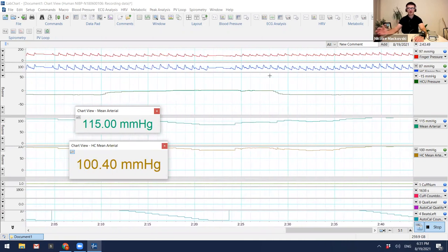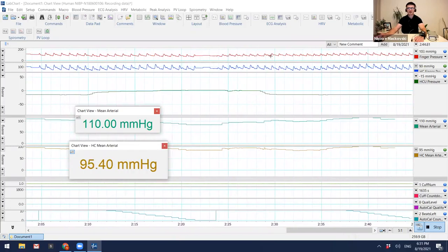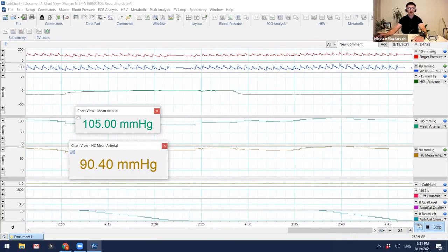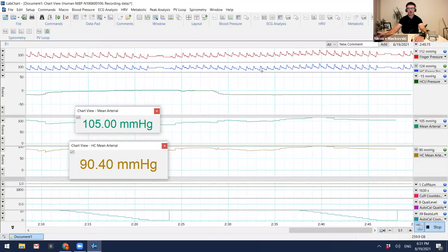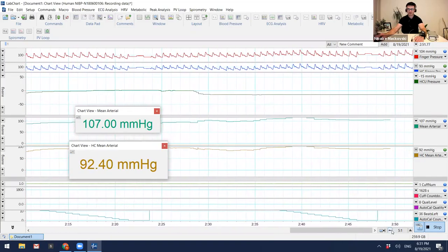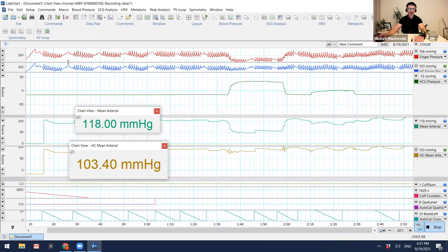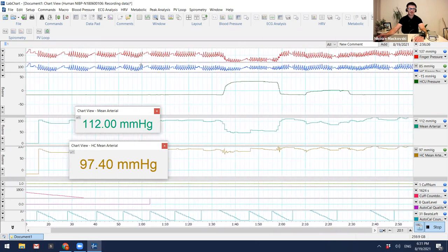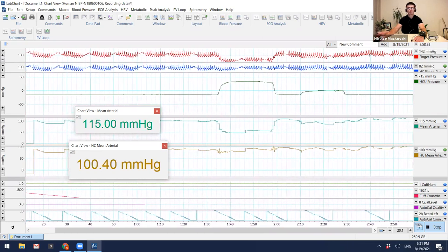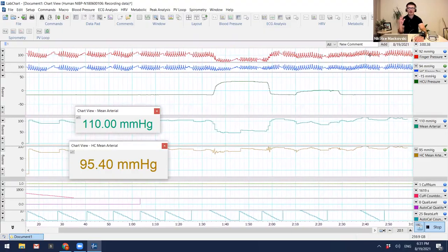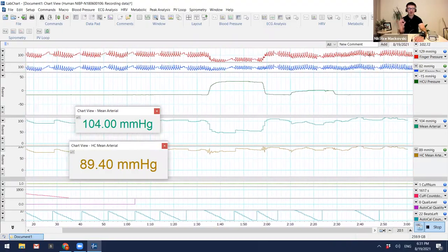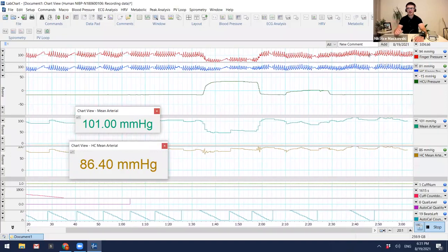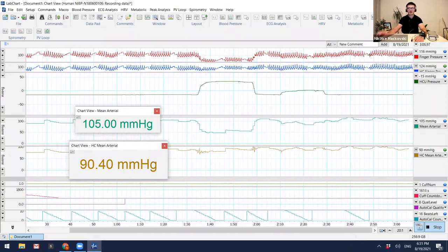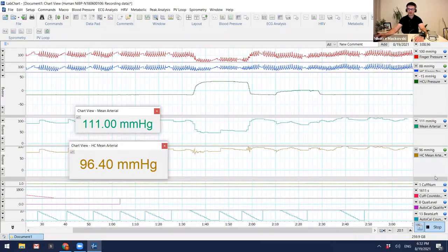As you can see, after a few minutes of demonstrating this, now there's fewer actual set points. There's fewer autocal points. So if I zoom out a little, notice how we had autocals every 10 beats. Now it's much longer because the set point has been found. We found the correct unloaded diameter.